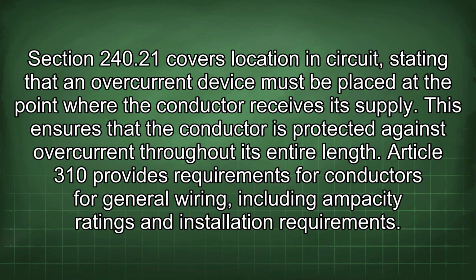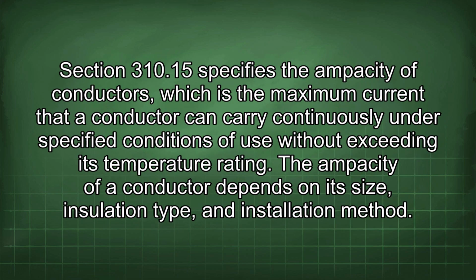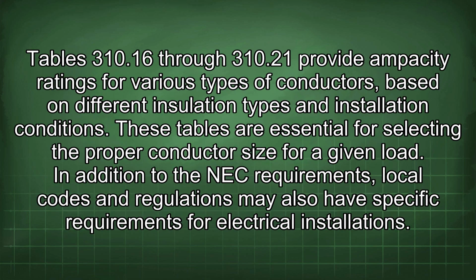Article 310 provides requirements for conductors for general wiring, including ampacity ratings and installation requirements. Section 310.15 specifies the ampacity of conductors, which is the maximum current that a conductor can carry continuously under specified conditions of use without exceeding its temperature rating. The ampacity of a conductor depends on its size, insulation type, and installation method. Tables 310.16 through 310.21 provide ampacity ratings for various types of conductors based on different insulation types and installation conditions. These tables are essential for selecting the proper conductor size for a given load.